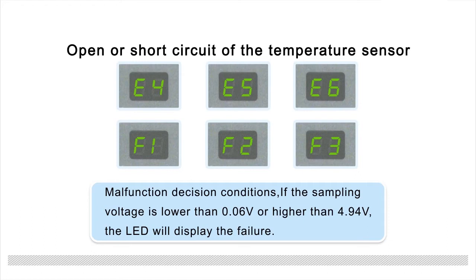Malfunction decision conditions: If the sampling voltage is lower than 0.06 volts or higher than 4.94 volts, the LED will display the failure.